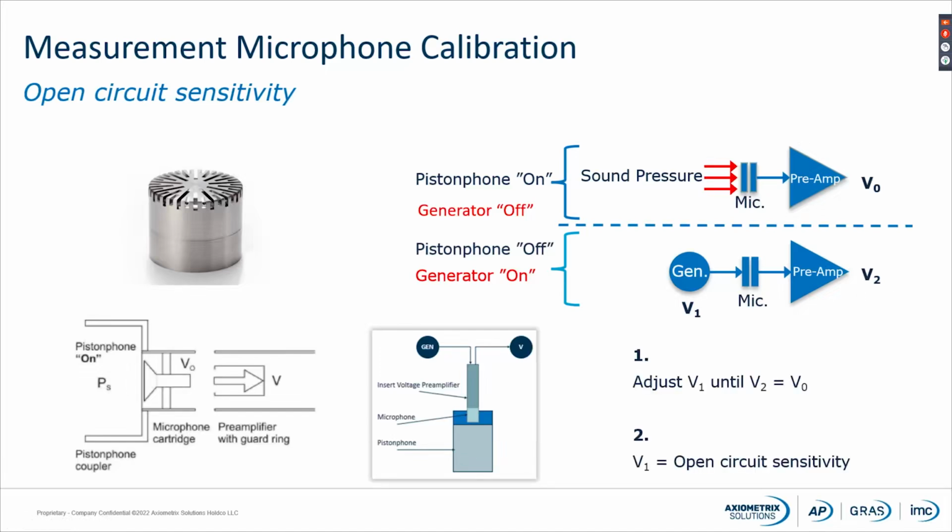We are trying to adjust V1 until the output is equal to what we measured before with the piston phone.